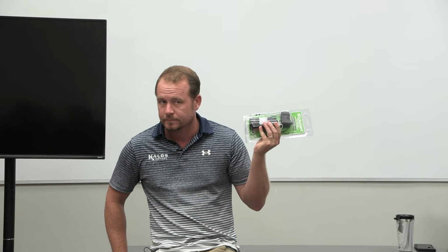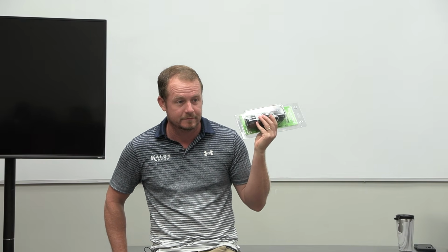Once that's all said and done, then you're going to go to a hard start kit. Now, let's say this unit is 3 months old and it has a locked compressor. Are you going to put a hard start kit on it? Trick question, you are, right? And why are you going to? See if you can get the unit right. You want to try to get it running, right?